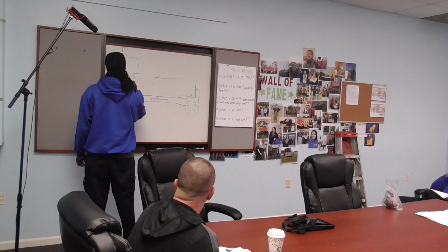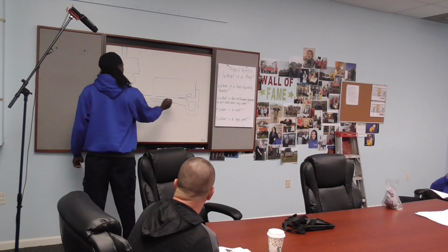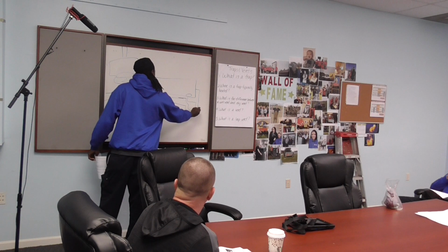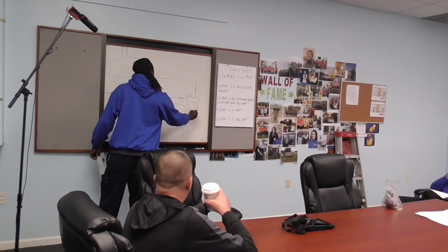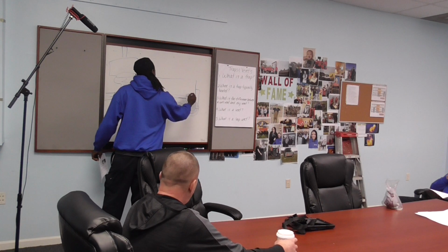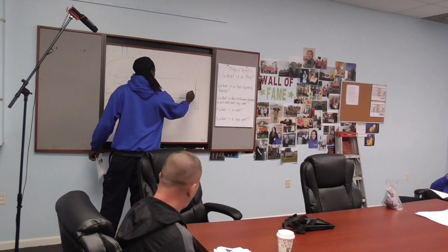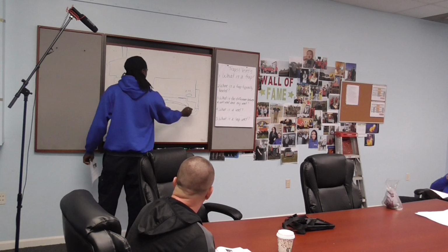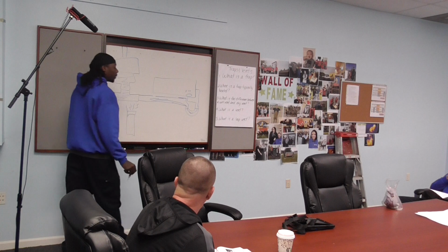Once that water flushes out that toilet, it's pulling the seal out of this trap. So you're lowering the water seal in the trap, and you're pulling air from this drain, and it makes that sound. And you're losing your trap seal. So then you start smelling sewer gases after a while that come through the tub.